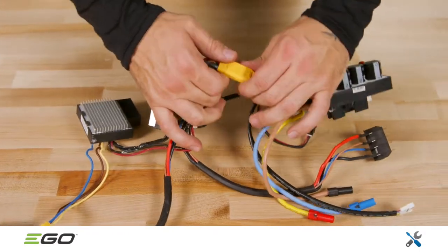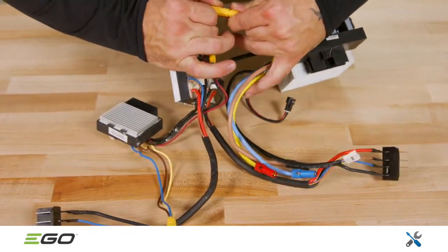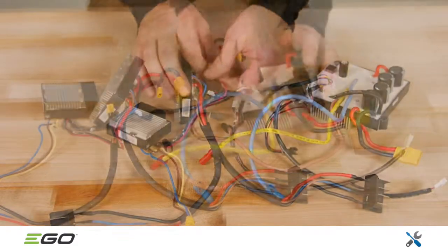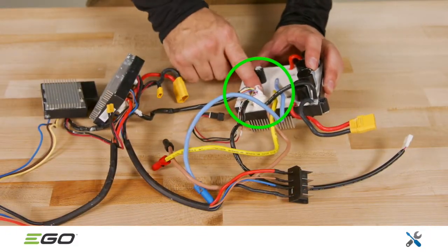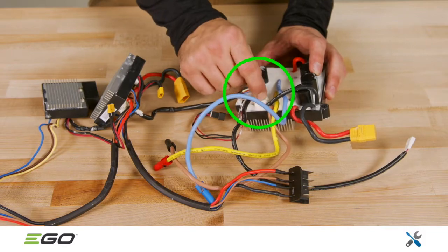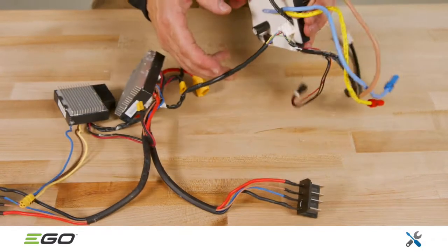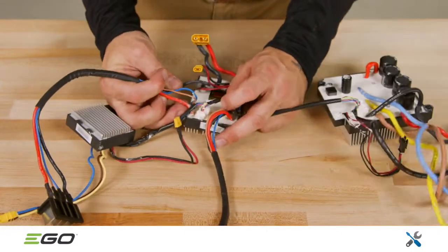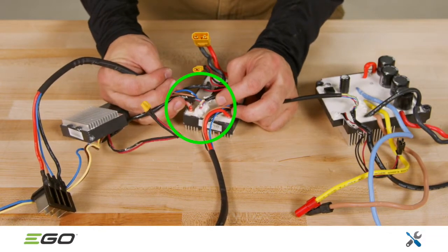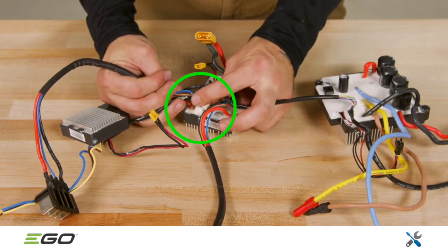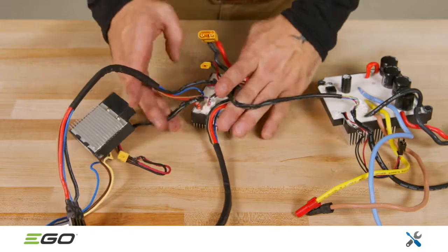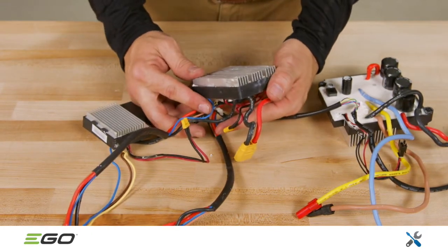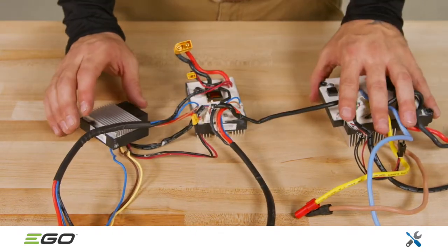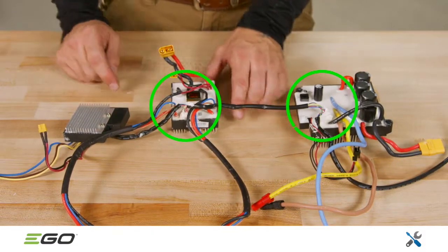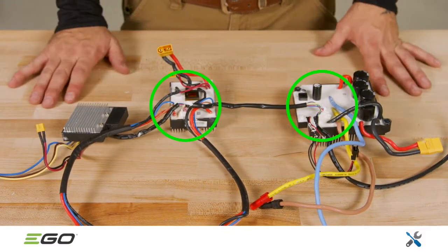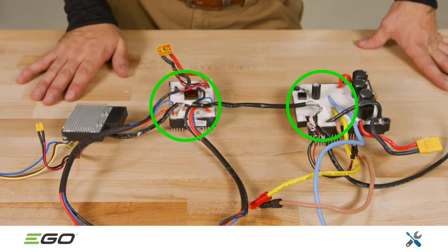To replace the main PCBA, disconnect the yellow connectors shown here. Then carefully remove the silicone from the ribbon connector and disconnect it. When replacing either of the other PCBAs, the silicone from the ribbon connector on the BMS PCBA must be carefully removed. This will disconnect it from the main PCBA and the Self-Propel PCBA. When reattaching either of the ribbon connectors, be sure to use silicone to waterproof the connection.